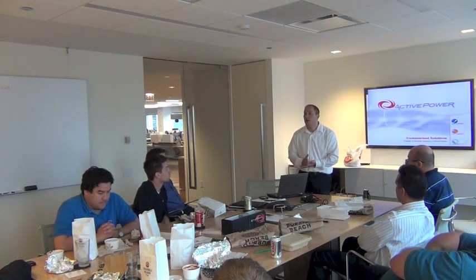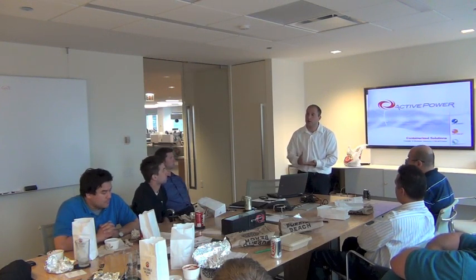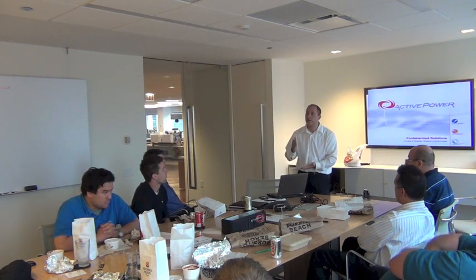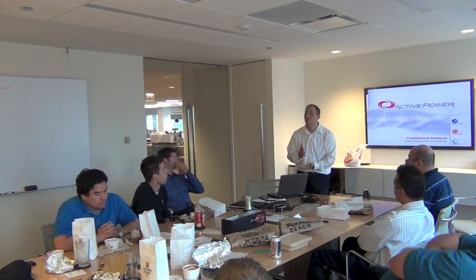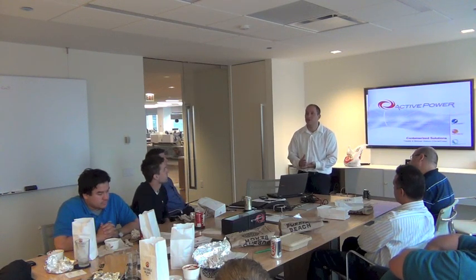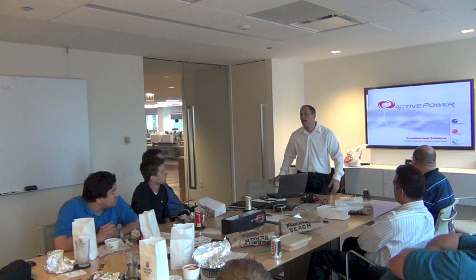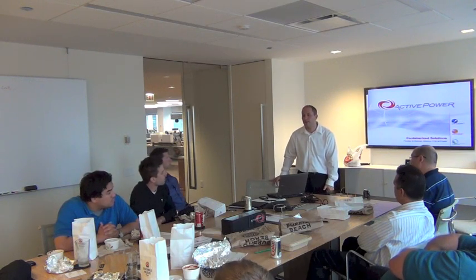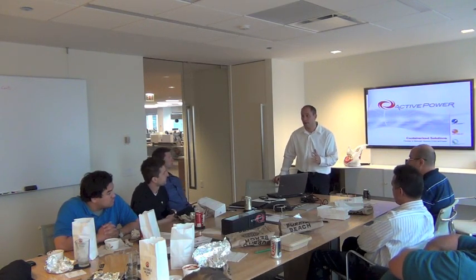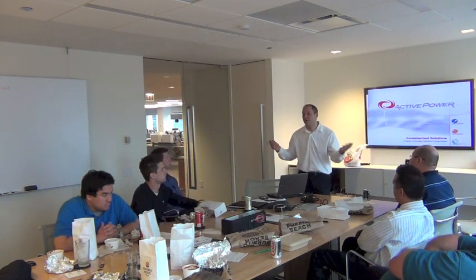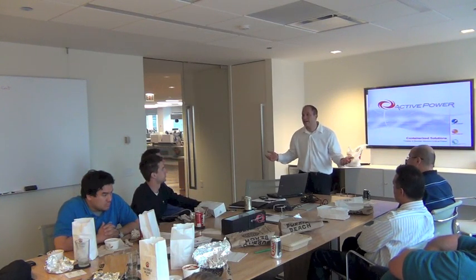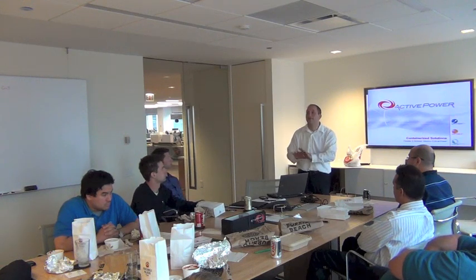We want to make sure who the generator manufacturer is and how long it takes for the generators to come up to speed. We want to know who the switchgear guys are, how they're defining an outage, the under and over voltage trips, the under and over frequency settings when you're on generator. And we definitely design a system to work at 100% load, unless there are special conditions where the customer says, hey, I'm never going to load it. Here's what I'm doing: I'm paralleling 8 generators on the bus, I need more ride through time, I can guarantee all these generators to be up in 18 seconds, and I'm never going to load my UPSs past 60%, even in a failure mode.